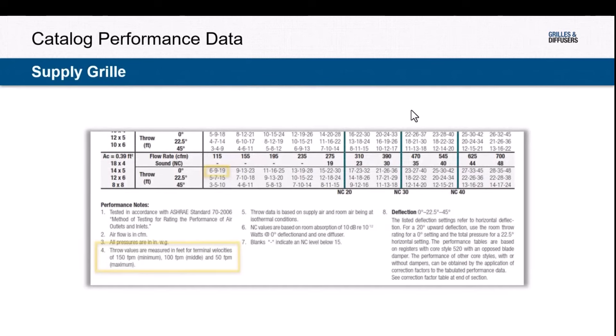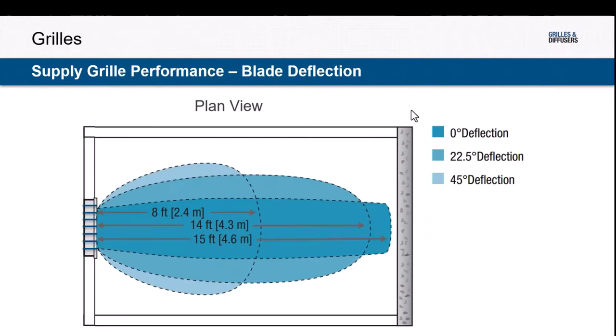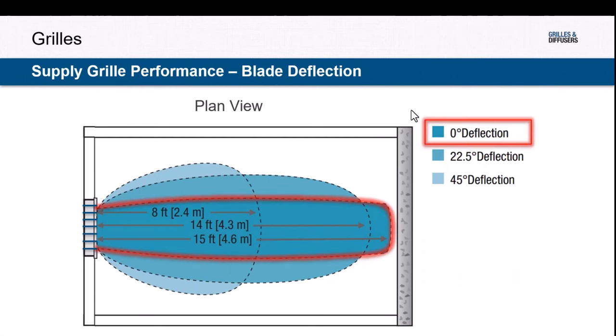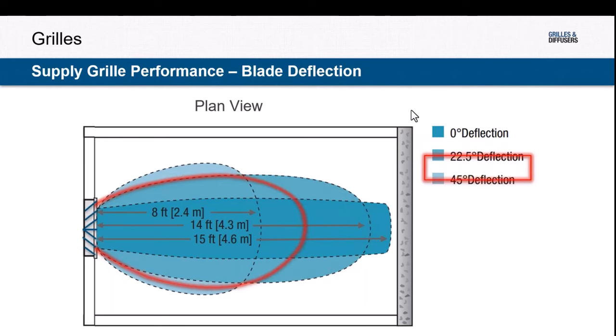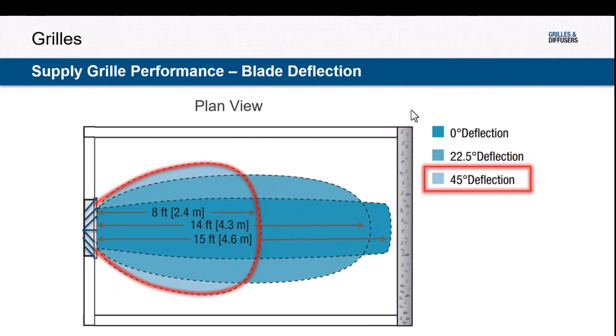In the case of grills, we catalog throw lengths at three different blade angles, because the blades are adjustable on site. Looking at a zero-degree deflection, we can see it gives a much narrower pattern that travels further, giving longer throw lengths. With a 22.5-degree deflection, the wider spread results in shorter throw lengths. And with 45 degrees, it shortens even more. When designing a space and selecting the appropriate product, that spread is important.